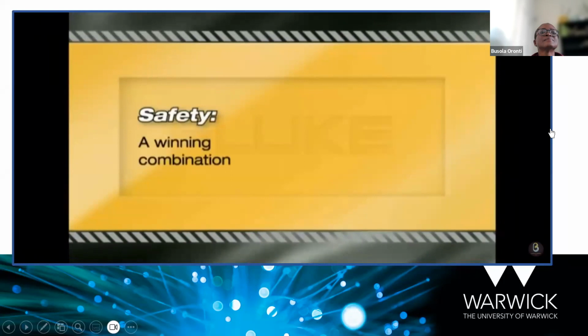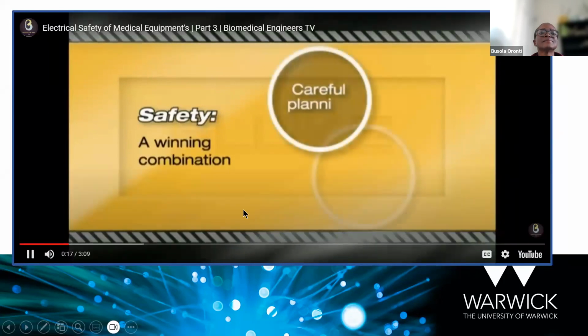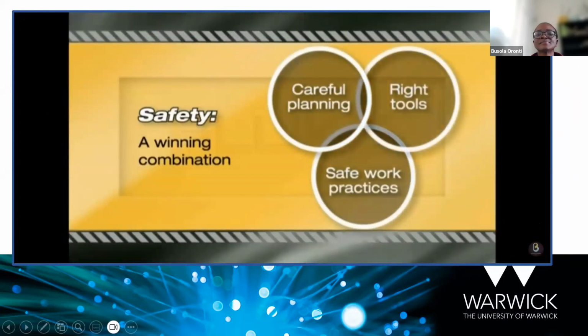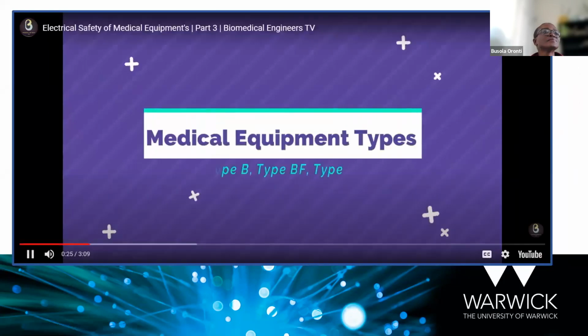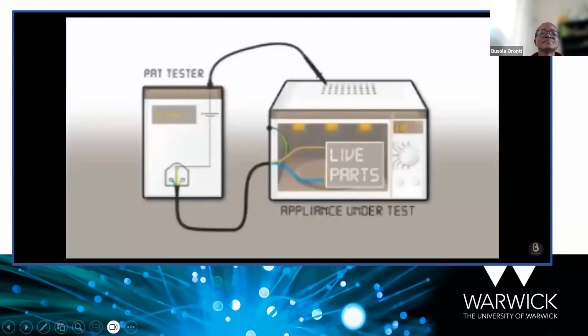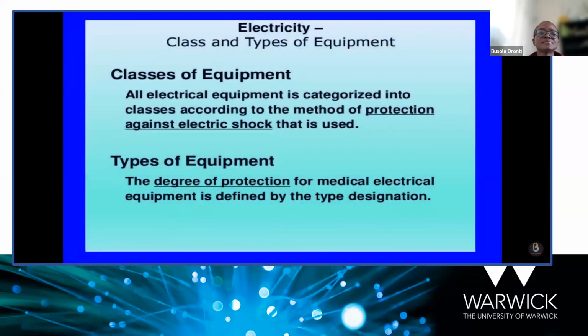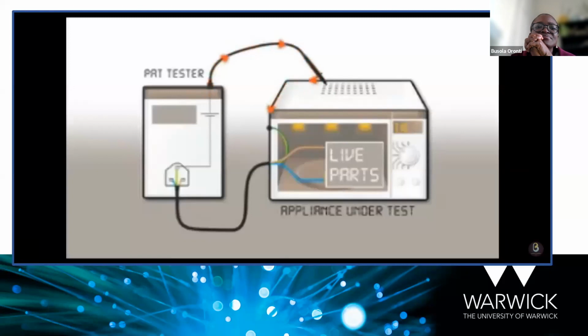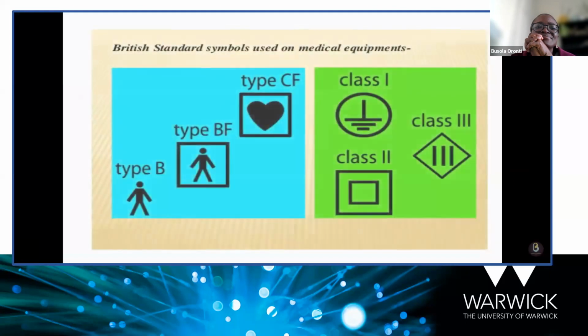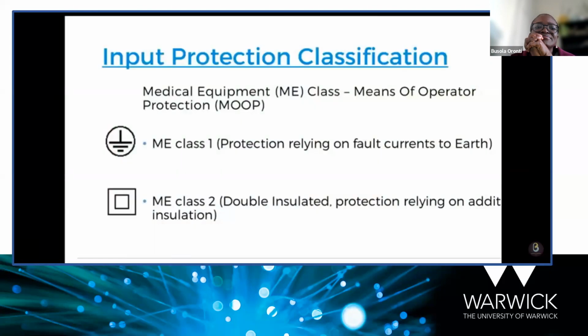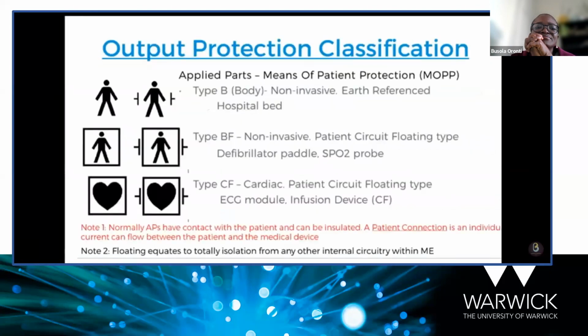Biomedical Engineers TV. If you are watching this video first time, I encourage you to begin with the first part of this video to understand the electrical safety standards of medical equipments. In this last video, we will cover up the medical equipment type. The class of equipment defines the method of protection against electric shock. The degree of protection for medical electrical equipment is defined by the type designation. The reason for the existence of type designations is that different pieces of medical electrical equipment have different areas of application, and therefore different electrical safety requirements. For example, it would not be necessary to make a particular piece of medical electrical equipment safe enough for direct cardiac connection if there is no possibility of this situation arising.